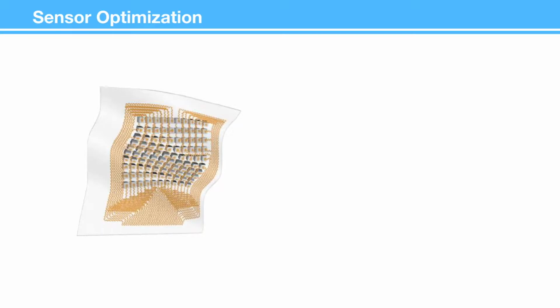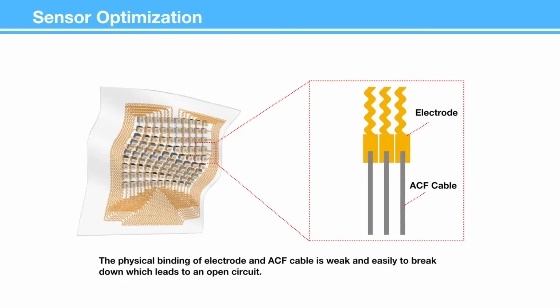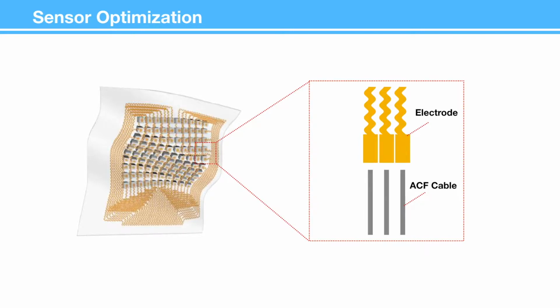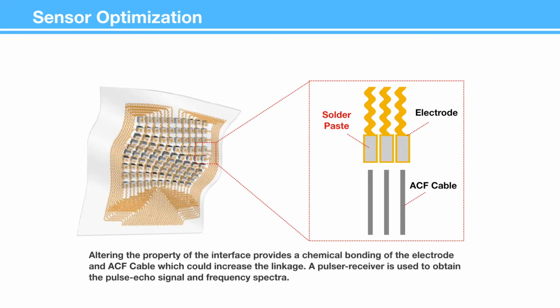And for the sensor optimization, as we can see in the picture, this is the sensor that we have discussed before. To zoom in on the sensor, we can see there are actually 2 parts, which are the electrode and the ACF cable. However, the linkage between the electrode and ACF cable is actually a physical bonding, which is kind of weak and easy to break down, which leads to an open circuit. And the solution for the sensor optimization is to put solder paste between the electrode and ACF cable. So we alter the property of the interface and provide a chemical bonding of the electrode and the ACF cable so that the linkage will be strengthened.